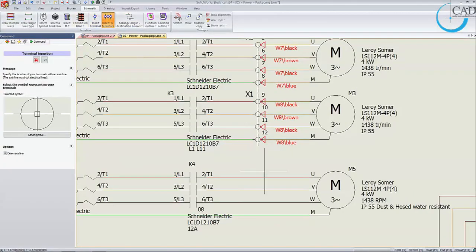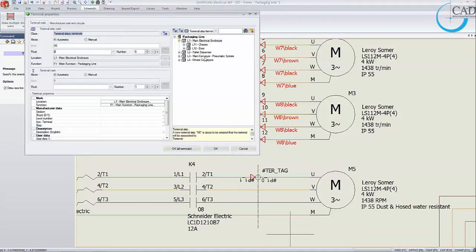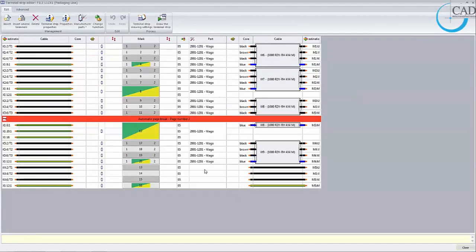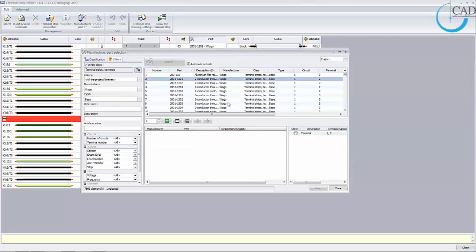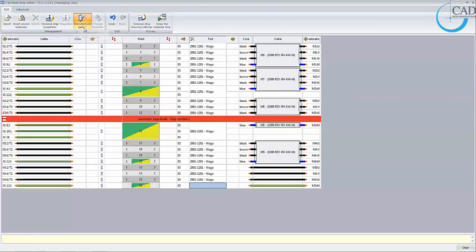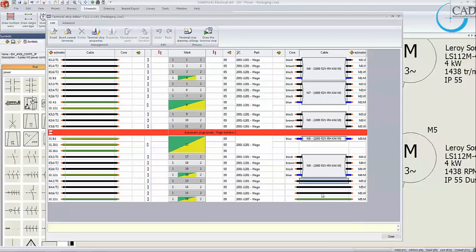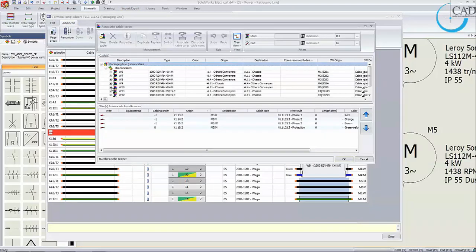We'll now add the terminals and associate them to X1. We can also add manufacturer details to the terminals — it will add one manufacturer part to three terminals, and one more unique part to the last terminal. Remember the W10 cable inserted in the line diagram? We would now like to associate the cores of that W10 cable with these four cores here. We can do that simply by selecting 'associate cable cores,' choosing the cable, selecting the cores, and associating them. Easy as that.